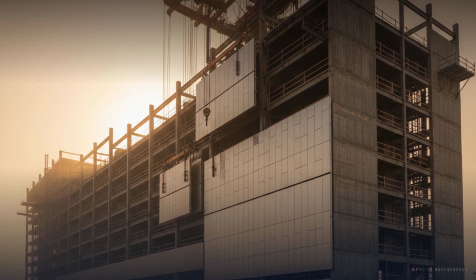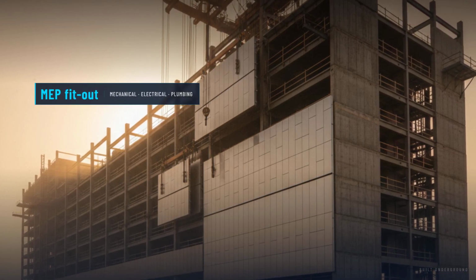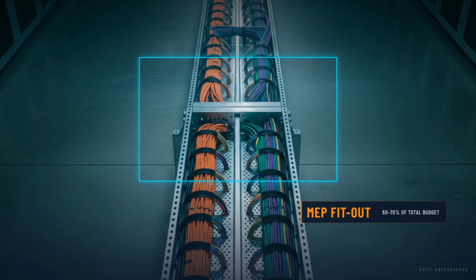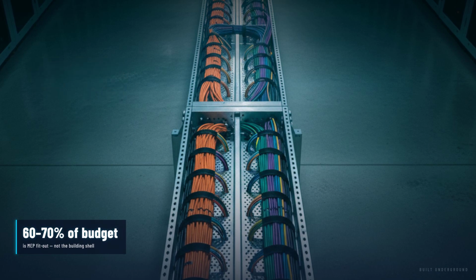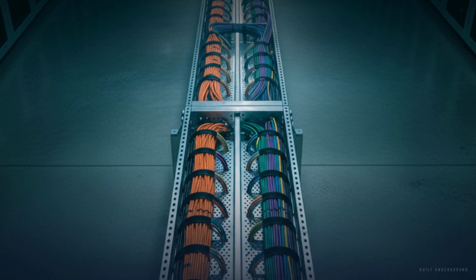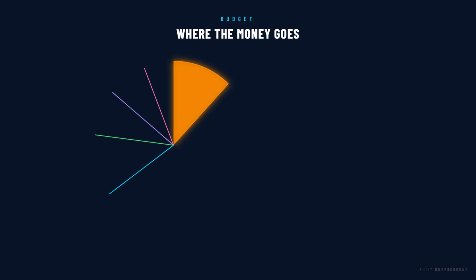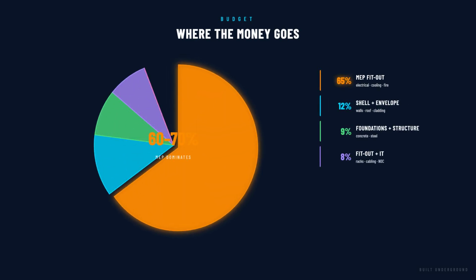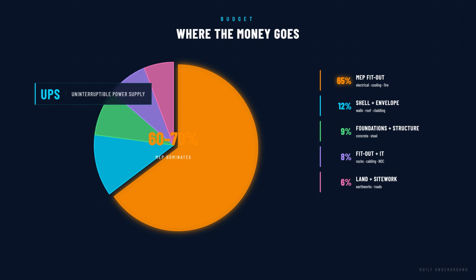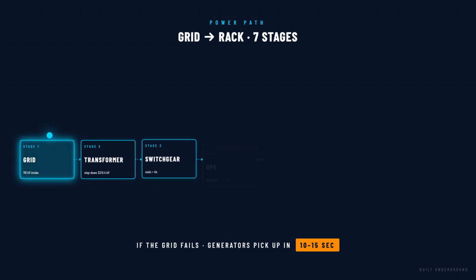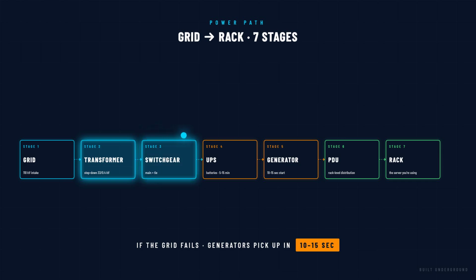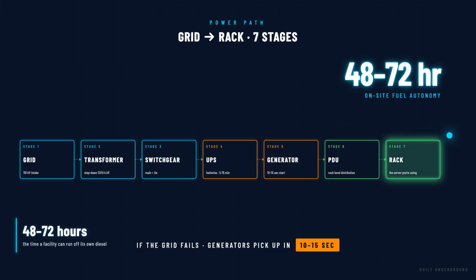Now comes the part that makes data centers unique: the MEP fit out, mechanical, electrical, and plumbing. This is where 60 to 70% of the construction budget goes. Not into the walls and roof, but into the systems inside them. The electrical infrastructure alone is staggering. Power comes in from the grid at high voltage, gets stepped down through transformers, distributed through switchgear, backed up by UPS systems and banks of batteries, and finally delivered to each rack through power distribution units. If the grid fails completely, diesel generators kick in within 10 to 15 seconds. Some facilities keep enough fuel on site to run independently for 48 to 72 hours.